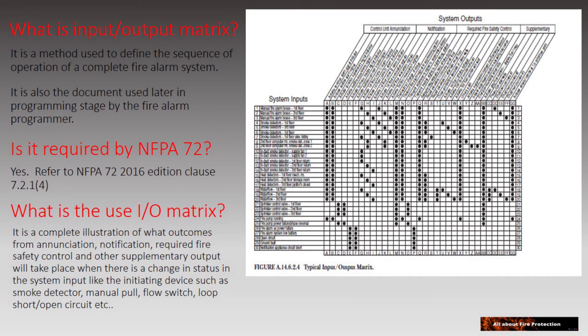So what is an input and output matrix? It is a method used in fire alarm for designers and programmers to show their intended sequence of operation for the complete fire alarm system. Basically, once the input and output matrix is done, it can be used at the same time for programming of the fire alarm control panel.